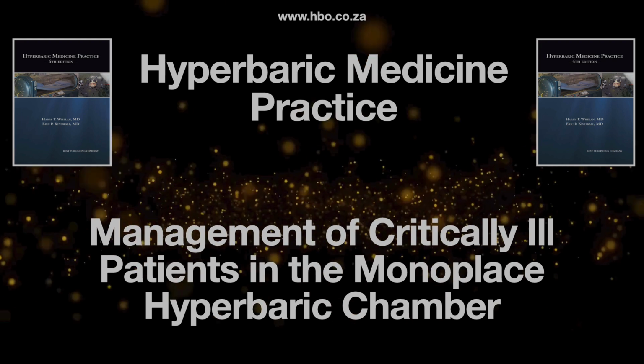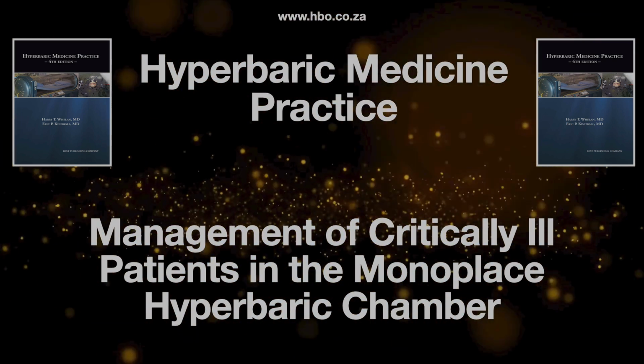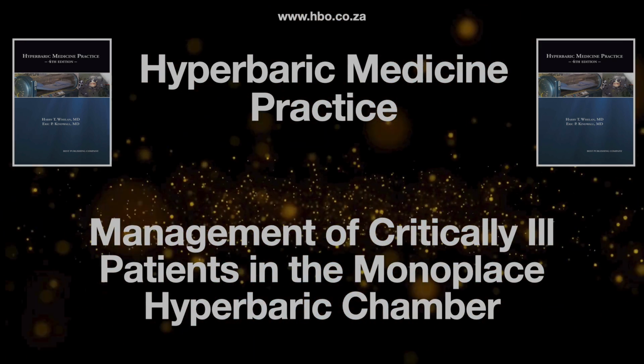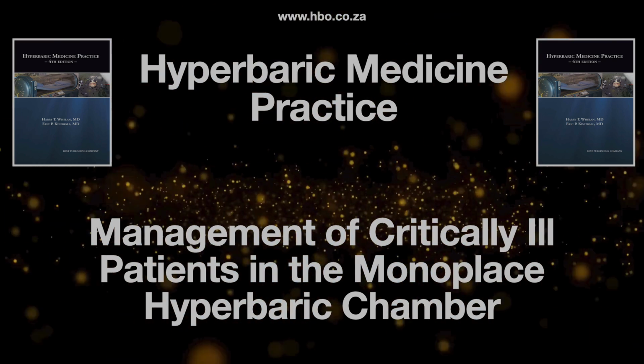Key things are respiratory rate, the actual volume they exhale, PEEP level, airway pressures, the O2 supply pressure to the ventilator, and if they're taking any breaths on their own. End-tidal CO2 monitoring is really valuable too.